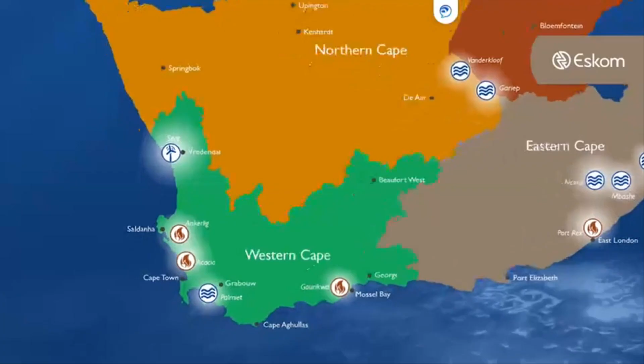Palmiet Pumped Storage Scheme provides 400 megawatts to the grid. We've got the upper dam and the lower dam. When we generate, the water comes from the upper dam through our penstock, goes to the turbine, and the turbine shaft is connected to the generator. When it produces electricity, we go up to the step-up transformer, then to the transmission yard, and then to the grid.